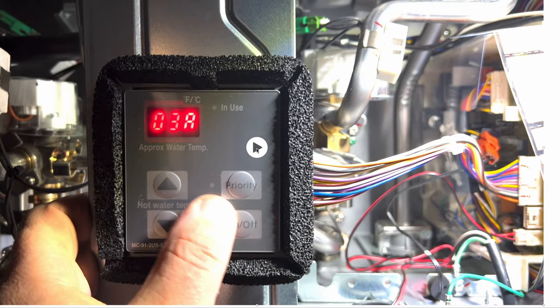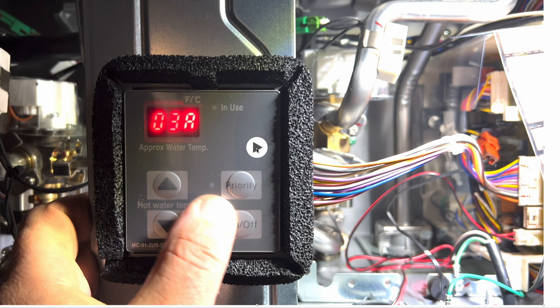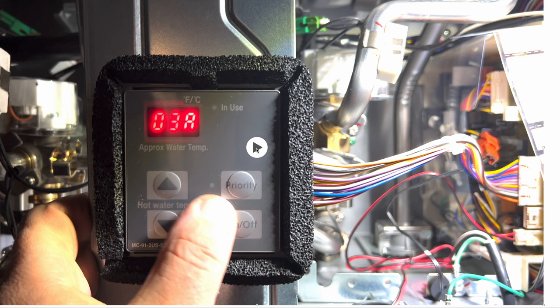Setting O3 is service soon. This feature reminds you that it is time for service. The default selection is A, service notification disabled. Selection B will notify you every 6 months. Selection C will notify you every year. And selection D will trigger the beep every 2 years. The notification is in a form of a beep. When the beep comes on, to cancel it, push on-off button 5 consecutive times. You can do that without entering this menu. You can push the on-off button five consecutive times at any time to cancel the beep. This will reset the notification until it's time for it again.